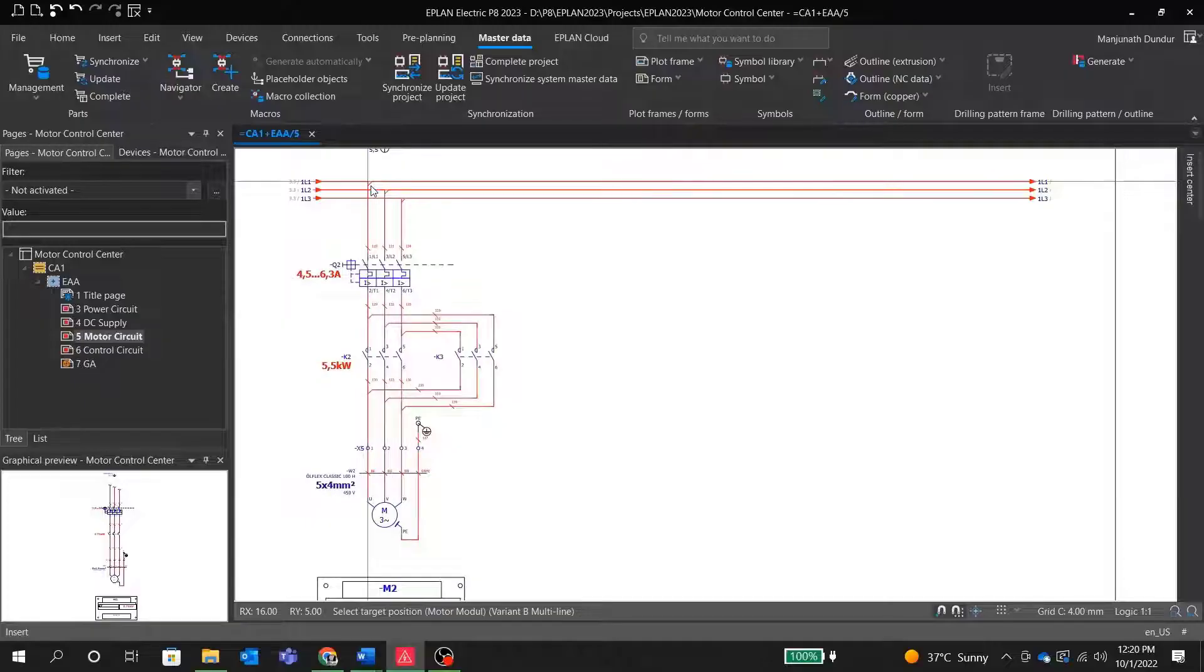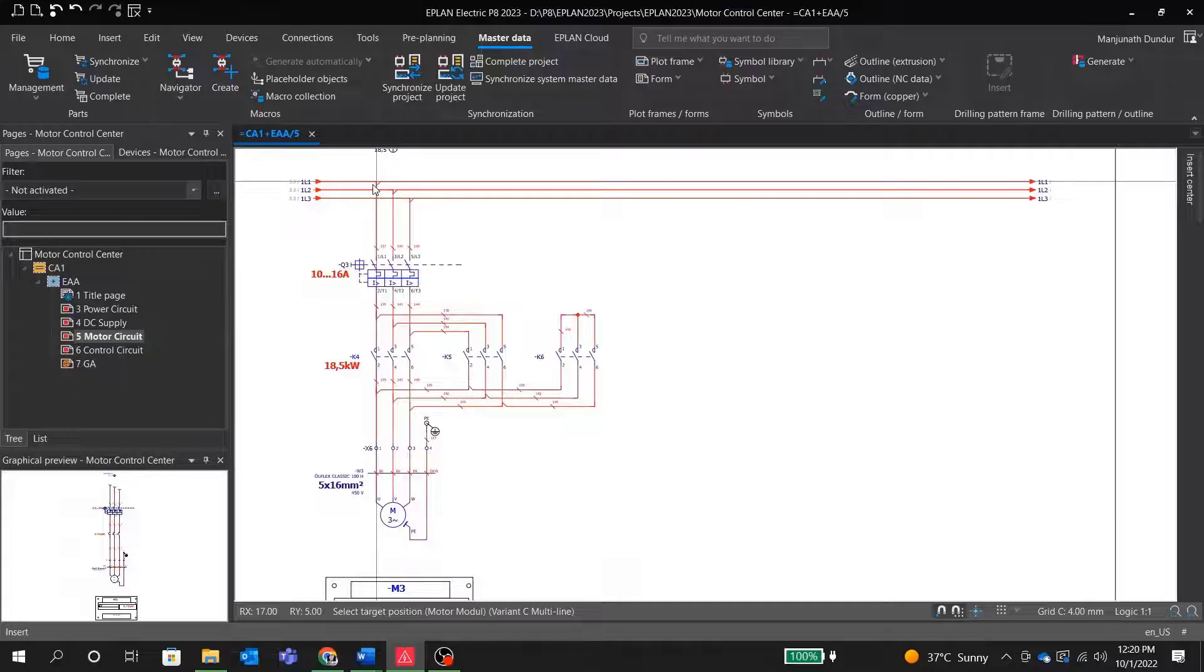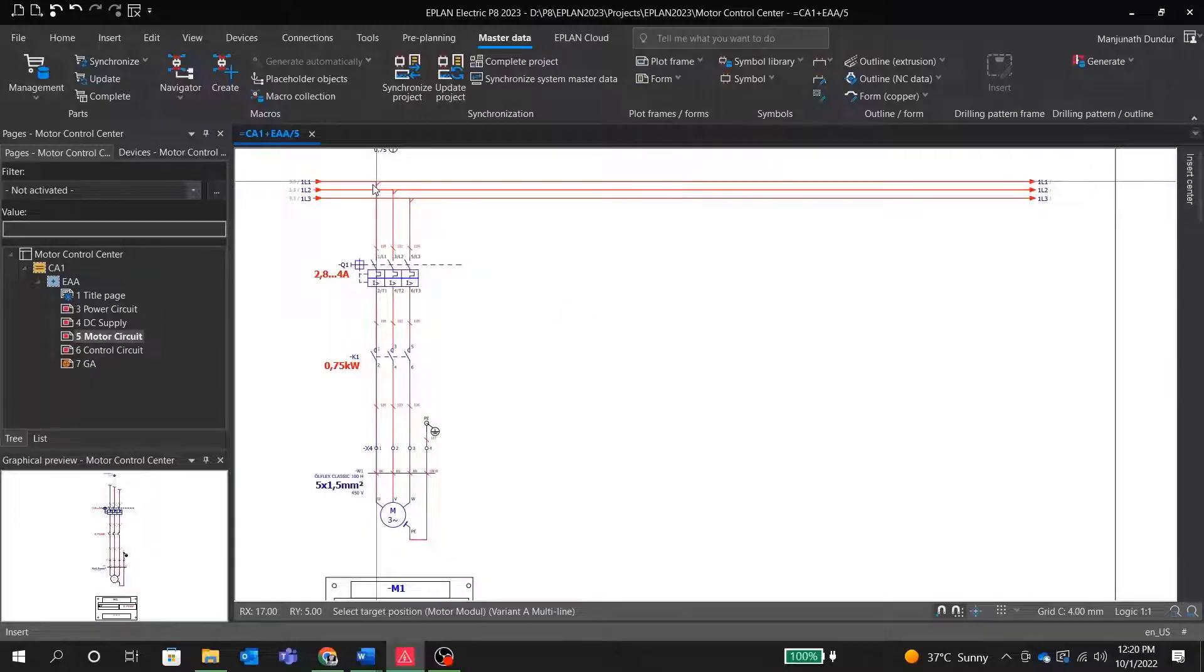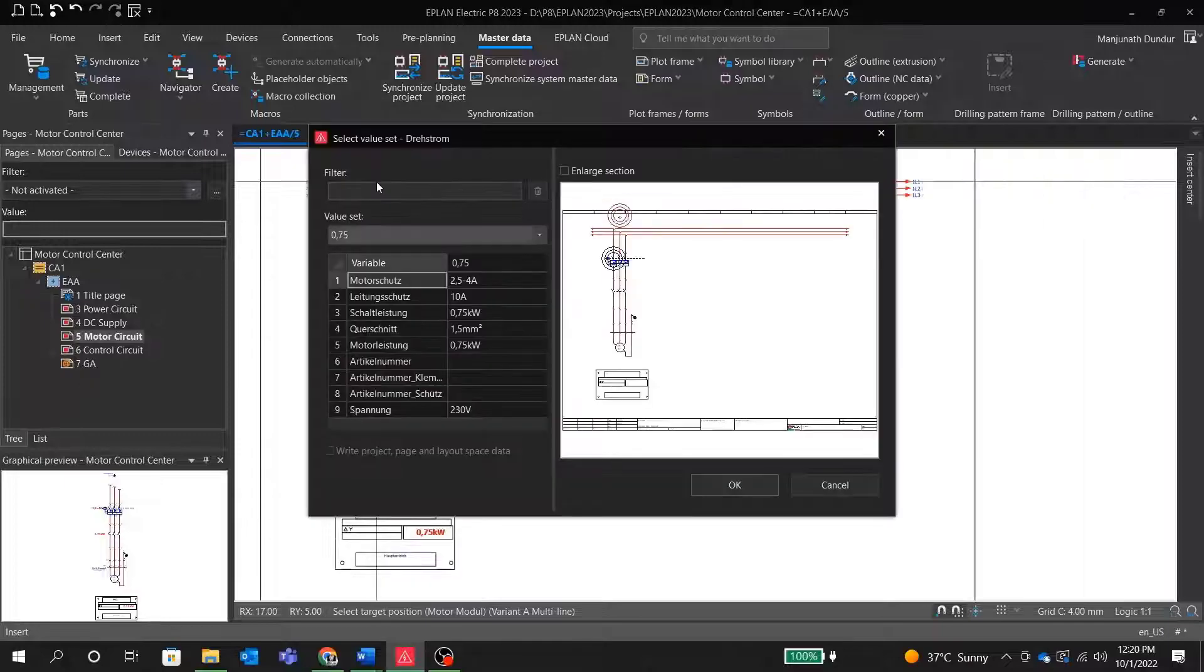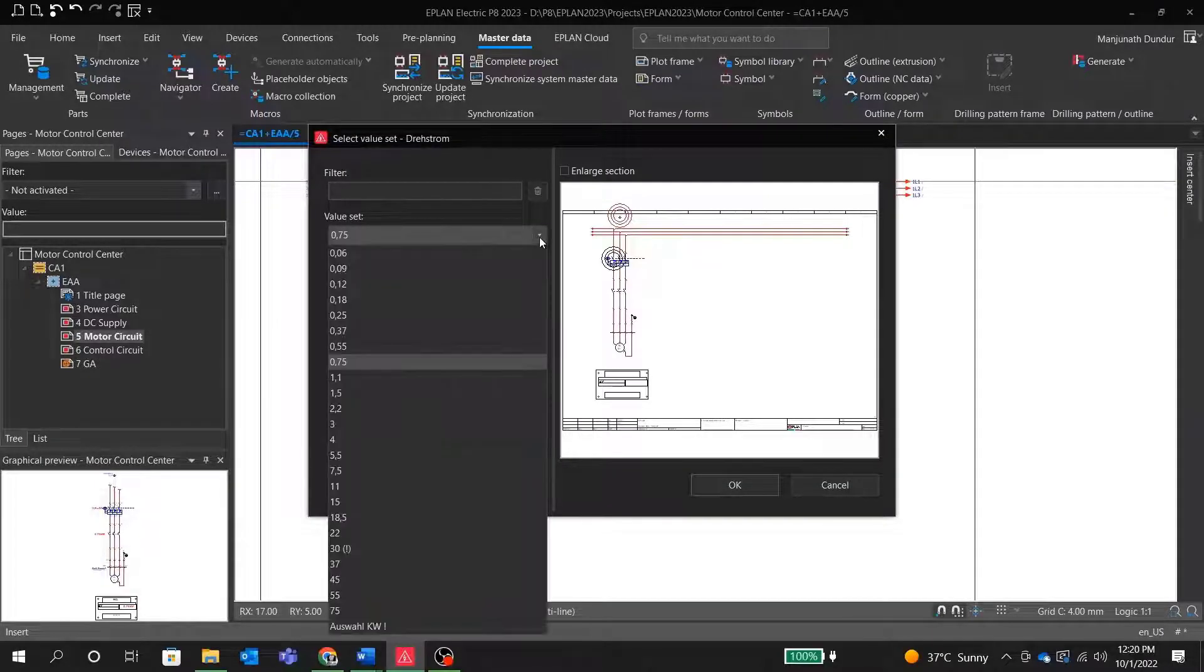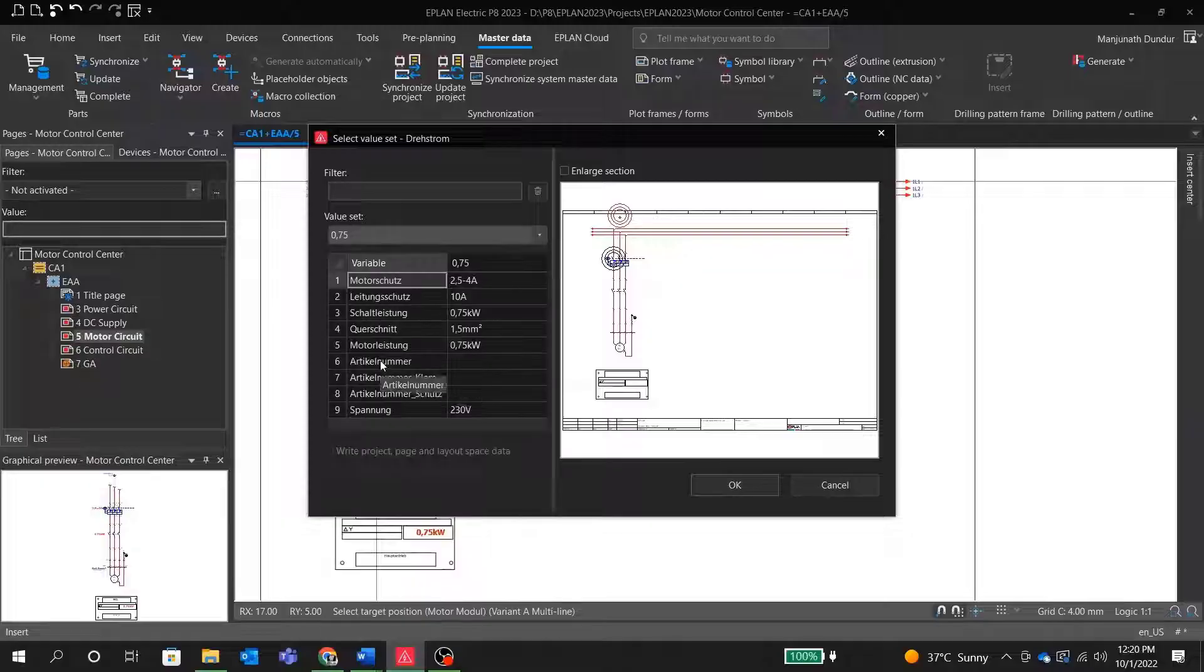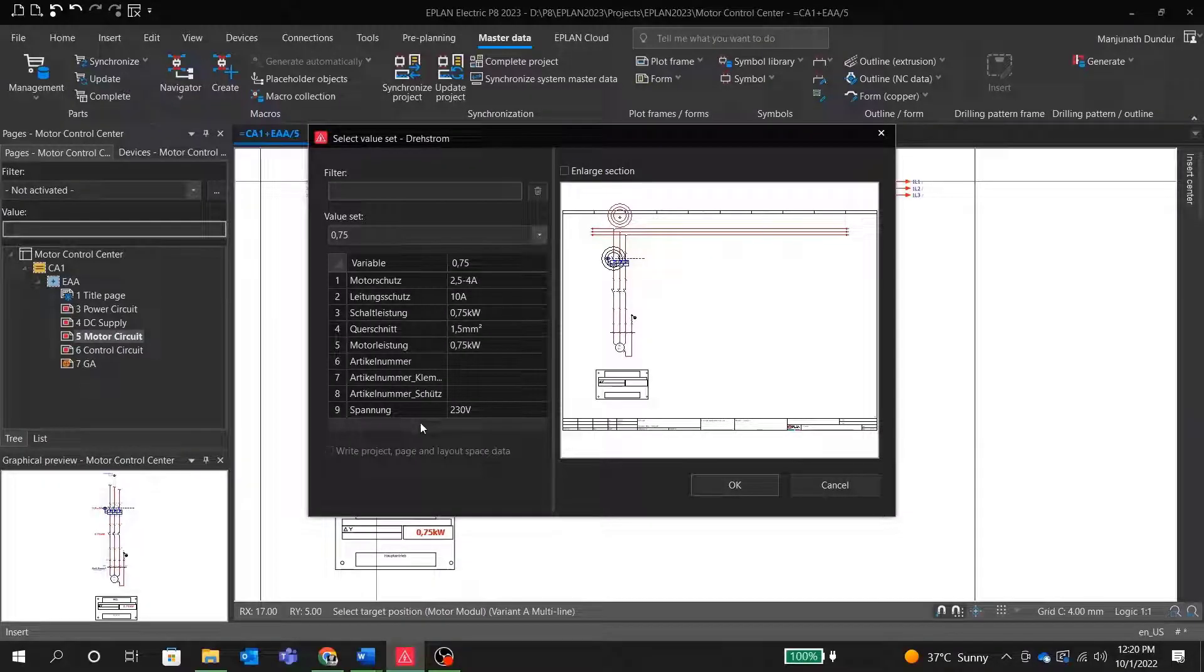And then we want to go ahead and insert our motor starter macro. This macro is a DOL type of motor starter. If we change a variant, we have a forward and reverse starter. Again, if you change a variant, you can see now we have a star and delta variant. So in short, the same macro can have different variants for different use cases. Similarly, we can have macro variants for soft starters and VFDs.